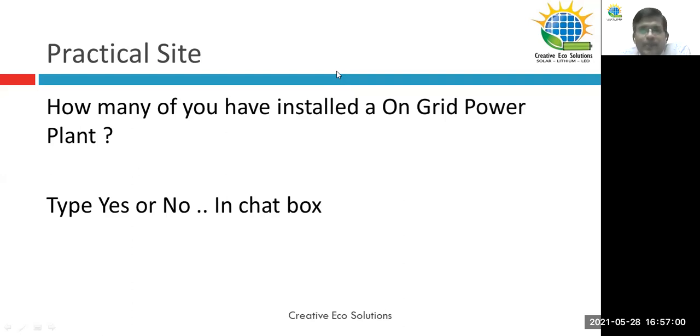So, how was your experience, sir, while installing a 1 megawatt plant? Actually, it is the first project we have done for a 1 megawatt solar plant, near Arbukote. The soil condition was very difficult to start the project for pushing the panel pillars, because the area we are excavating is sandy. So pushing was not able to achieve the levels for all the structure. That's the first problem we faced initially.